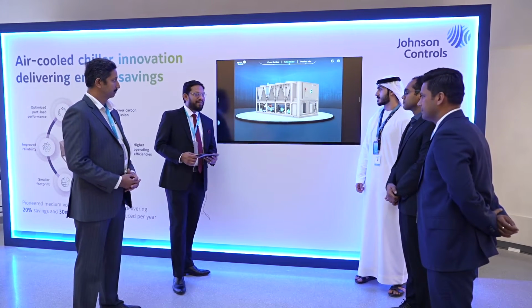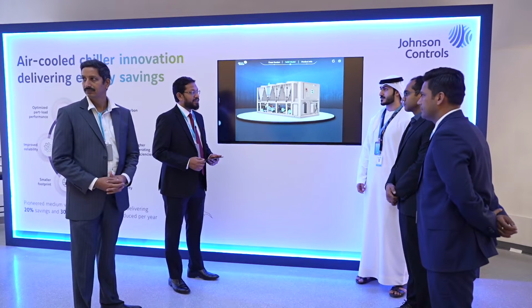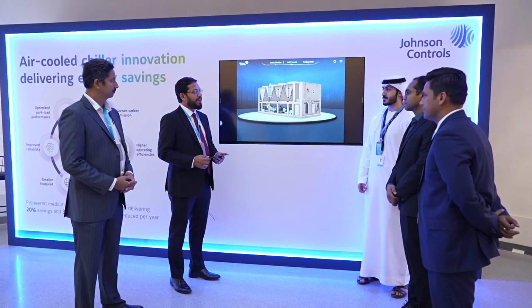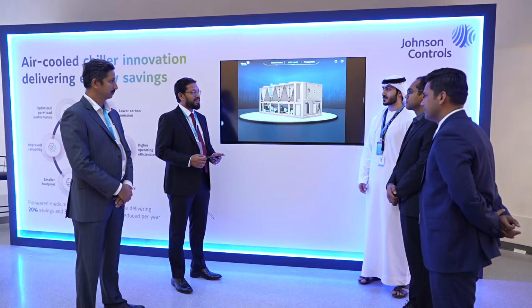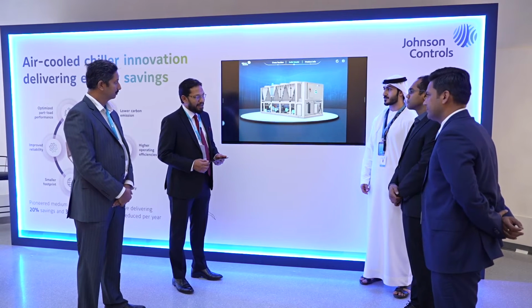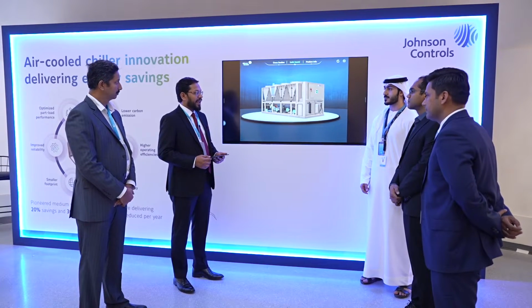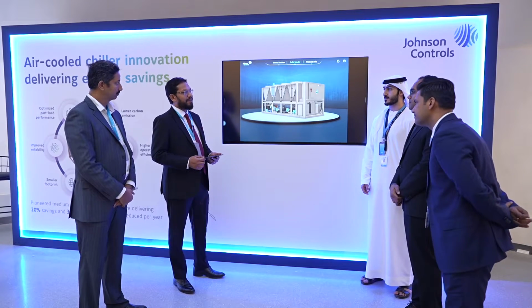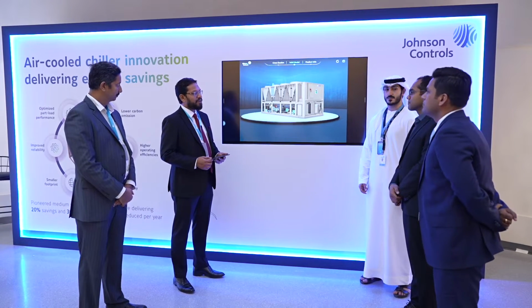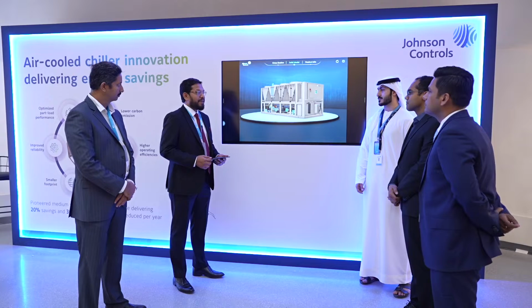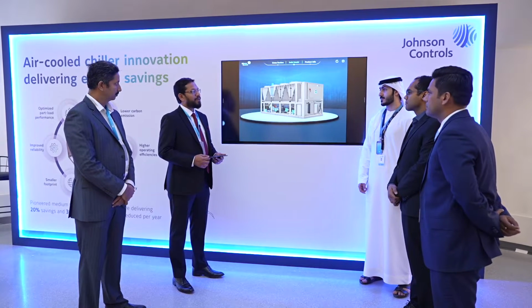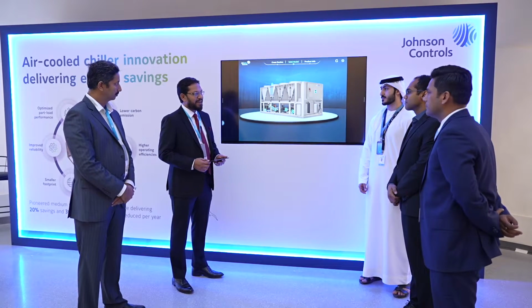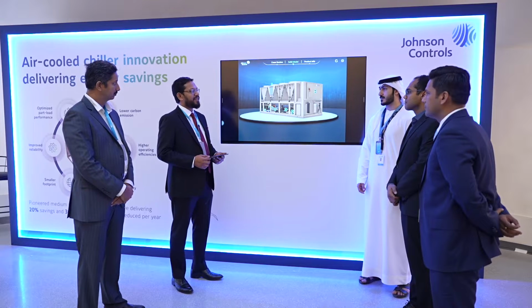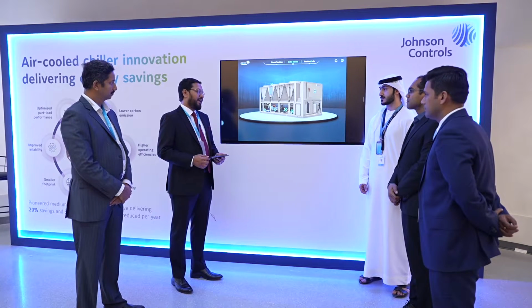In this AR stand, we wanted to present our flagship air-cooled variable speed drive chillers. We have a nomenclature called YVAA, which stands for York Variable Speed Drive Air-Cooled Generation, and A is the generation of the chillers. In these chillers, what we have been doing with York in our air-cooled machines is that when Johnson Controls does any product introduction to the market, they always lead the innovation and technologies into the market.